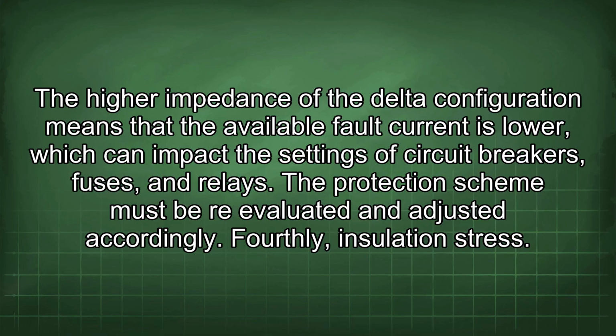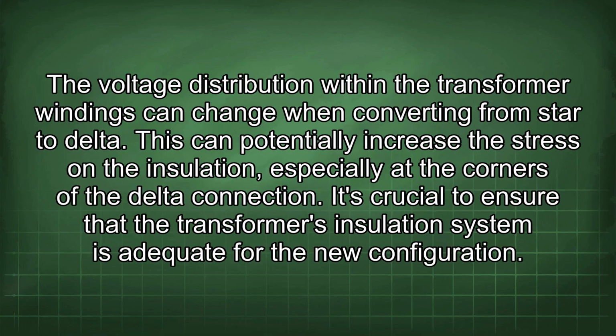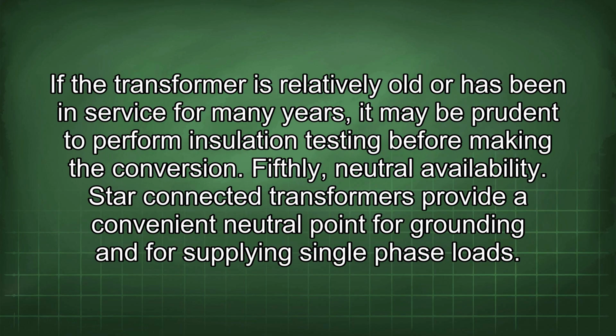Fourthly, insulation stress. The voltage distribution within the transformer windings can change when converting from star to delta. This can potentially increase the stress on the insulation, especially at the corners of the delta connection. It's crucial to ensure that the transformer's insulation system is adequate for the new configuration. If the transformer is relatively old or has been in service for many years, it may be prudent to perform insulation testing before making the conversion.